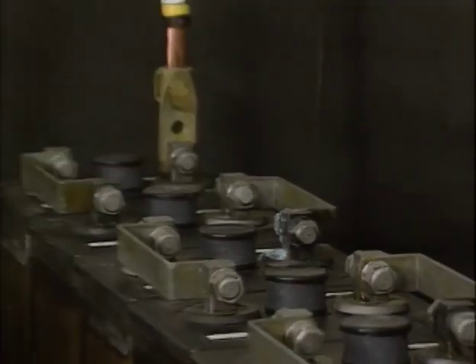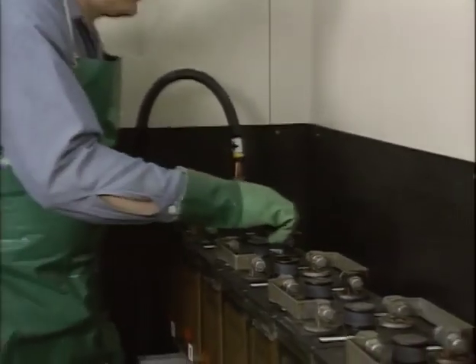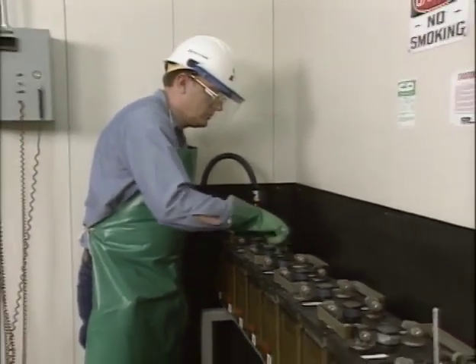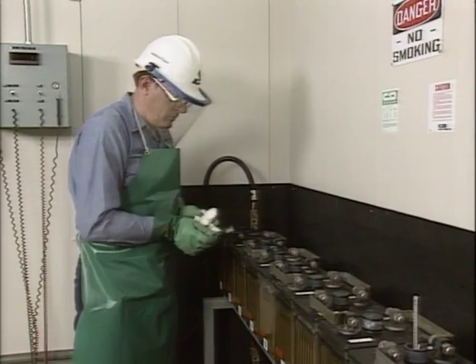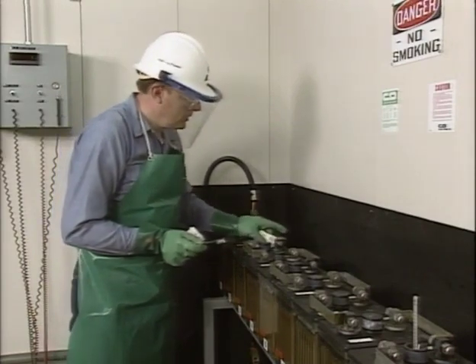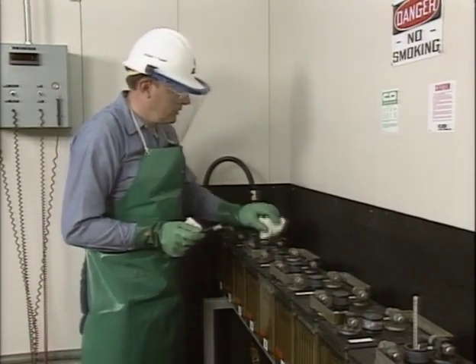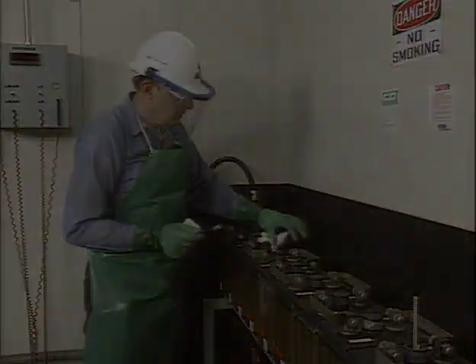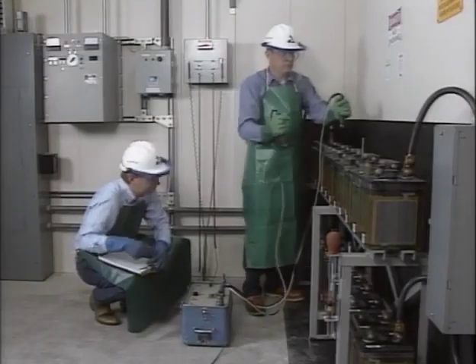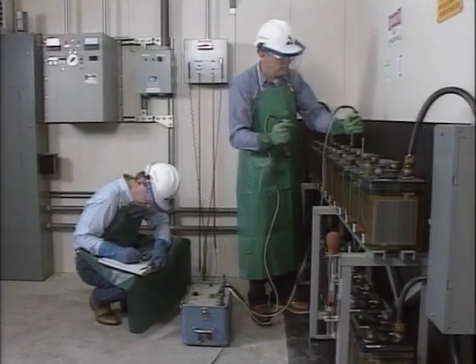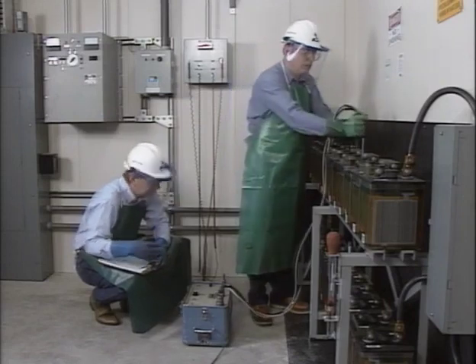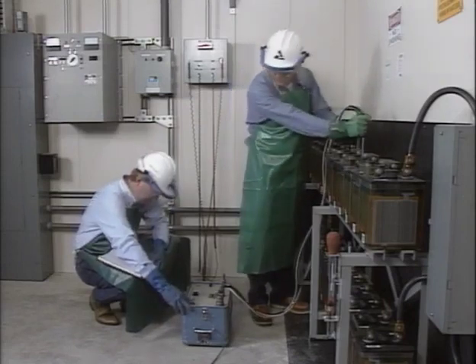Intercell connections with unacceptable resistance should be cleaned, tightened, and retested. If the resistance is still unacceptable, the cell might need to be disconnected from the battery so that the connections can be disassembled and given a more thorough cleaning. As shown in this part of the program, intercell connection resistance testing helps identify poor connections.